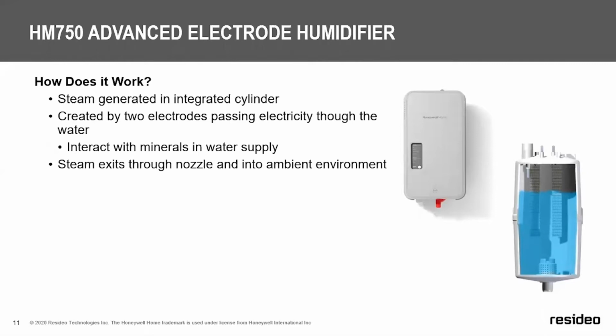The way this electrode steam humidifier works is steam is generated inside the steam cylinder. This is created by passing electricity across the two electrodes, which are your consumable component. The electricity will interact with the minerals in the water, causing a boiling action, which will then create steam, and that steam will enter the ductwork through the steam nozzle.